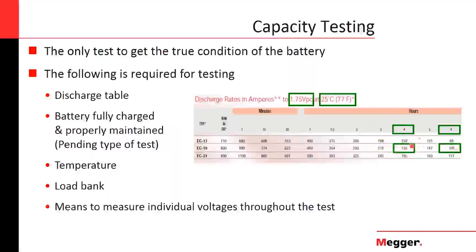Once you have all of this information, the battery needs to be fully charged and properly maintained. And this depends on the type of test as well, if it is a modified performance or a performance test. You need the temperature to be able to correct the result. There's a correction factor table.